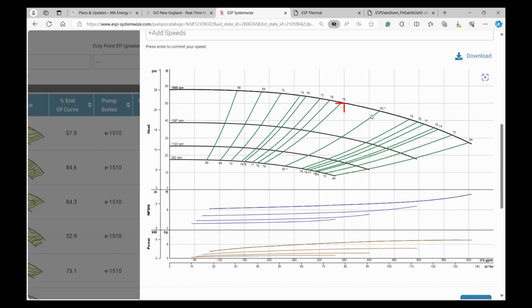And so they know their RPM, they know the motor current. And without getting too far into it, you can have points where the controls aren't sure whether they're at one or another. So if I have a sensorless device that's based off of motor current, or some sort of critical application, what I would typically avoid is sensorless directly on the unit with a flat curve.